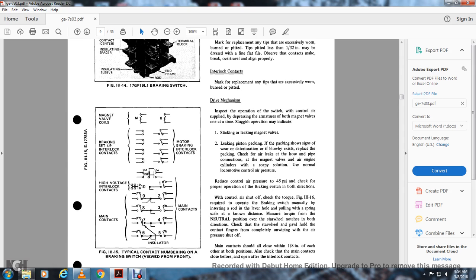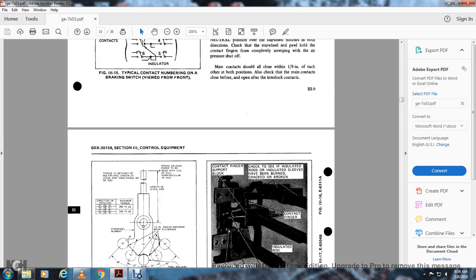With the control air shut off, check the torque with Figure 316 required to operate the braking switch manually. Insert the rod lever in the hole with the pulling of the spring scale with the known distance. Measure the torque from the neutral position over the star wheel notches in both directions. Check the star wheel and pawl hold the contact finger for the complete unwiping. With the air pressure shut off, main contact should also close within 1/8 of an inch of each other at both positions. Also, check that the main contacts close before and open after interlocking contacts.